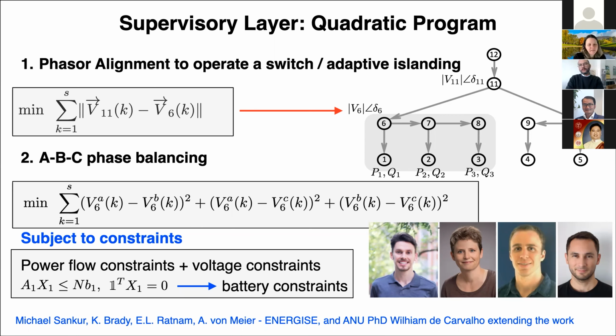In the US, they have a split phase transformer, which means it's not entirely separate if you're connected to A and B, there's a coupling across that. A split phase transformer means you can be connected to B and C, but it's not just B phase or C phase, it's a combination of those, and that's 120 volts to neutral for each, or 240 volts phase to phase.